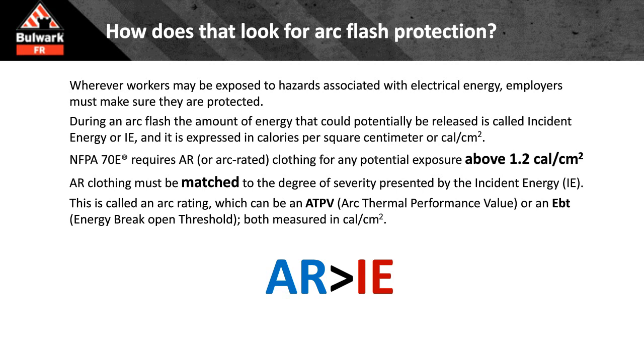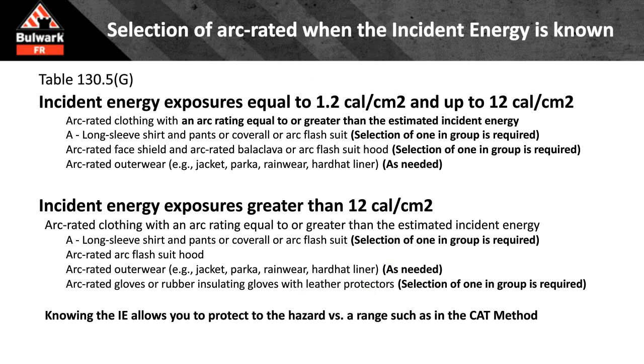For 70E, for our general industry electricians, it's real easy: between 1.2 calories and 12 calories, wear garments that are equal to or greater than the incident energy you're exposed to. This is because you know your incident energies — that's why that arc flash hazard assessment gets done, so you can dress with less. Ultimately, whether you use the simplified two-step approach or the tables, if you know your incident energies and you've done your study, typically 9 times out of 10 you'll be working with less PPE, because those tables are very conservative.